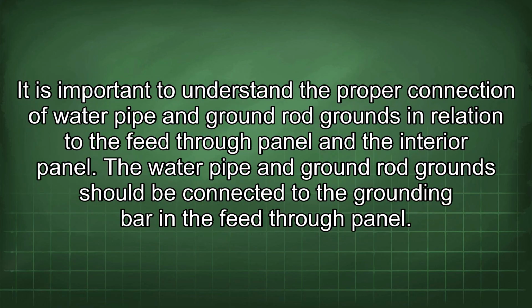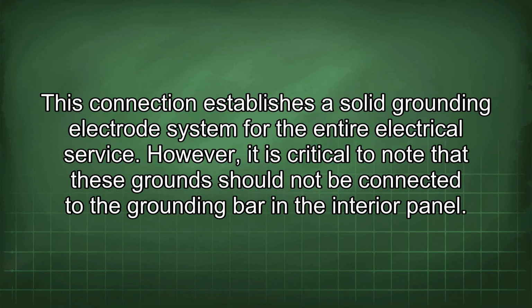It is important to understand the proper connection of water pipe and ground rod grounds in relation to the feed-through panel and the interior panel. The water pipe and ground rod ground should be connected to the grounding bar in the feed-through panel. This connection establishes the solid grounding electrode system for the entire electrical service.